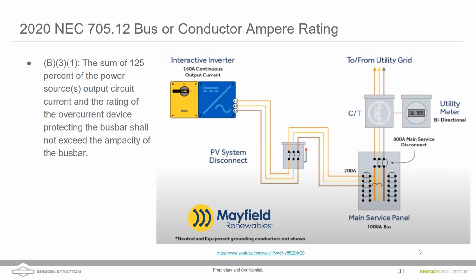This is the first way, and it isn't very common. Here we have a 1,000 amp bus, and this could be a 100 amp bus, it's just an illustration. We have a main service panel with a 1,000 amp bus, 800 amps coming in from grid, so we derated that main service, and 200 amps coming in from our solar side. It's not common to do it this way, but it has been done. You can land that 200 amp backfed breaker anywhere in that panel, and you're good to go. Next slide.